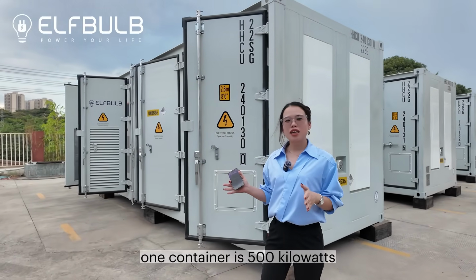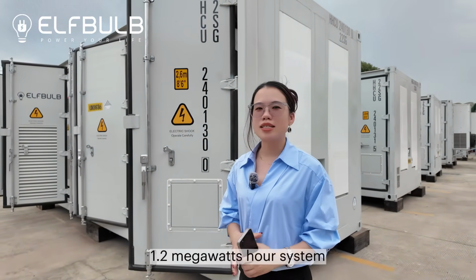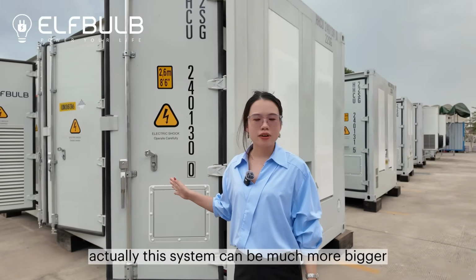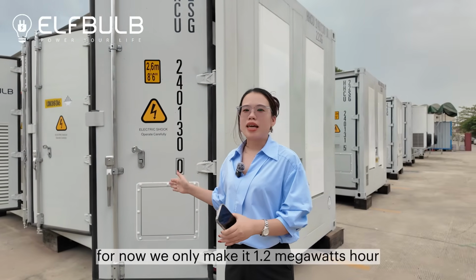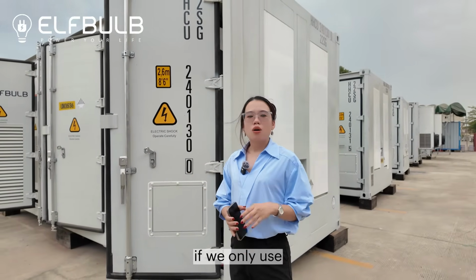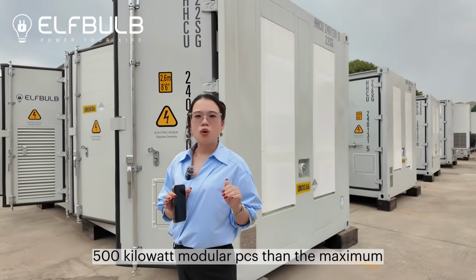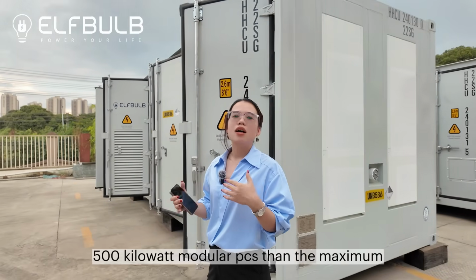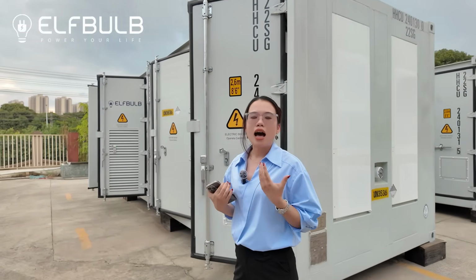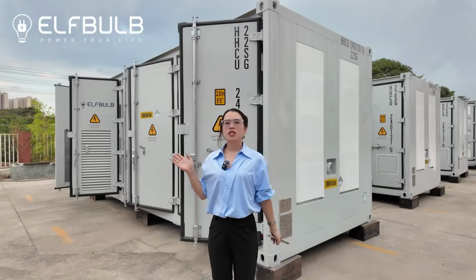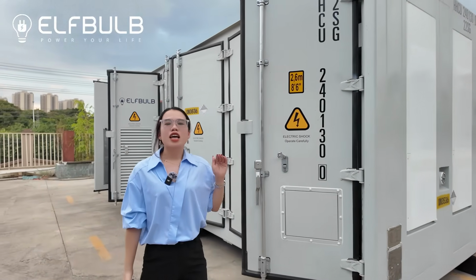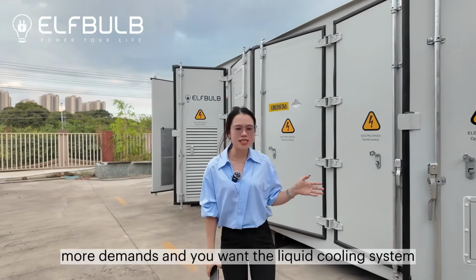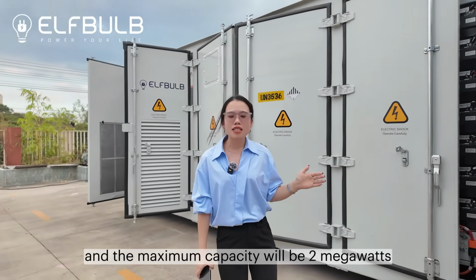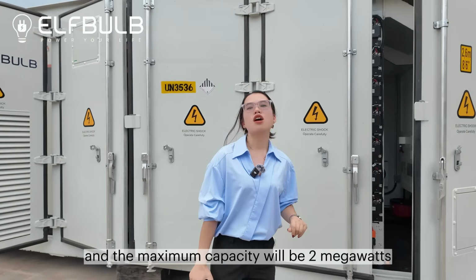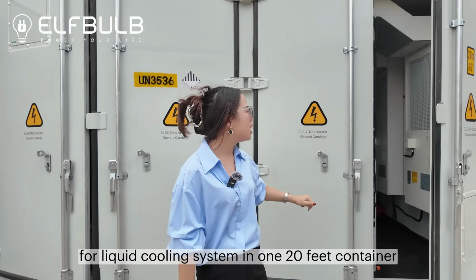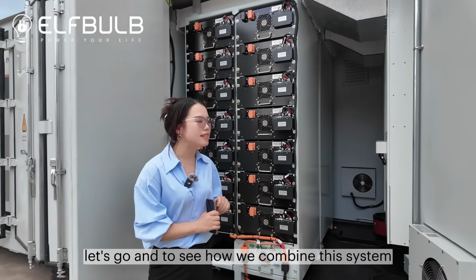One container is a 500 kilowatt, 1.2 megawatt hour system. Actually, this system can be much bigger, but due to the design, for now we only make it 1.2 megawatt hour. If we only use 500 kilowatt modular PCS, the maximum capacity we can do is 2 megawatt hour for a liquid cooling system. This one is an air cooling system, but if you have more demand and want a liquid cooling system, we can produce that too, with a maximum capacity of 2 megawatt hour for liquid cooling in one 20 foot container. Let's go see how we combine this system.